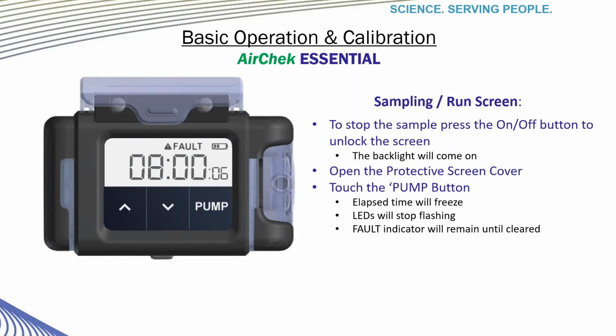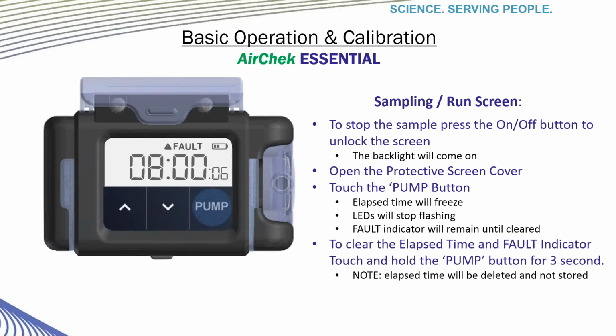If you have documented your flow time and documented that you had a fault indication in this case, you can clear the elapsed time and/or fault indicator by touching and holding the pump button for 3 seconds. It's important to note this will delete the elapsed time permanently. To turn off the pump, press the on-off button.